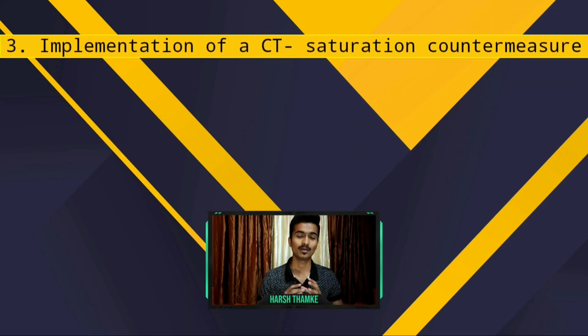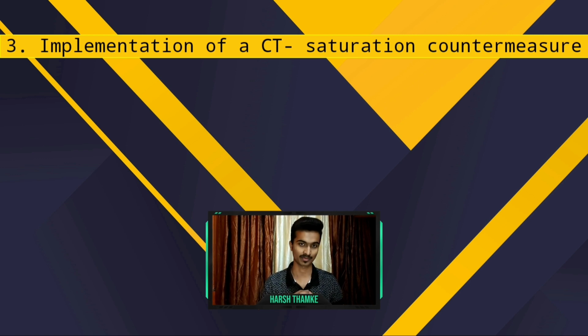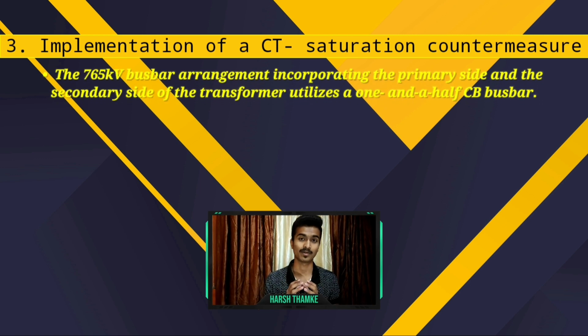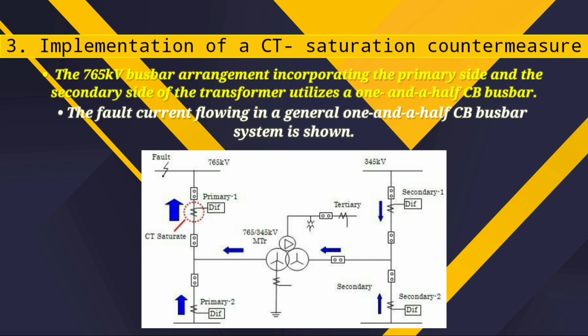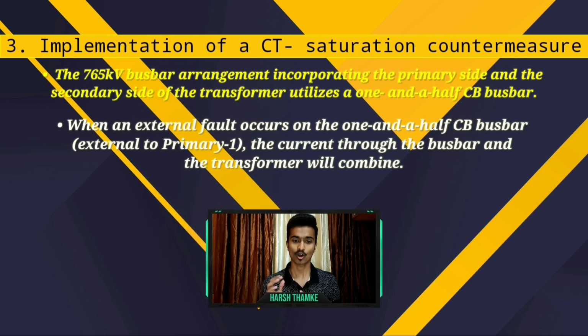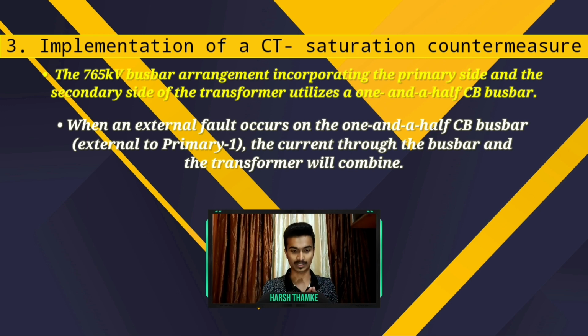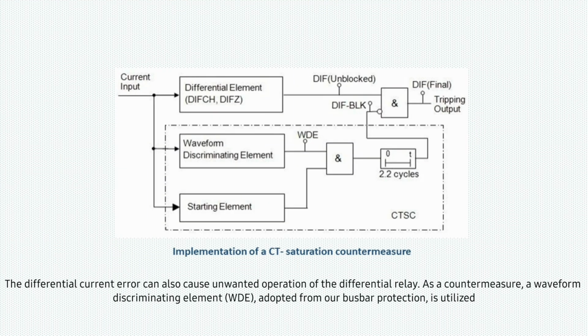And the third one is implementation of CT saturation countermeasure. The 765 kV busbar arrangement incorporating the primary side and secondary side of the transformer utilizes 1.5 CB busbar. The fault current flowing in the general 1.5 CB busbar system is shown in the figure. When an external fault occurs on the 1.5 CB busbar, or external to the primary, the current through the busbar and the transformer will combine. As shown in the figure, the differential current error can also cause unwanted operation of the differential relay.